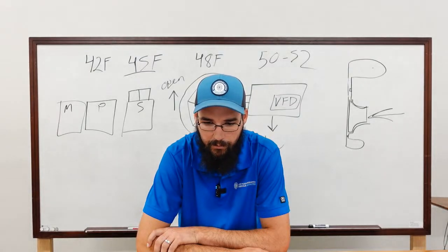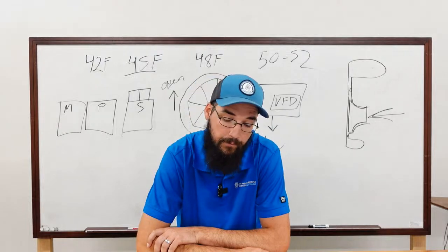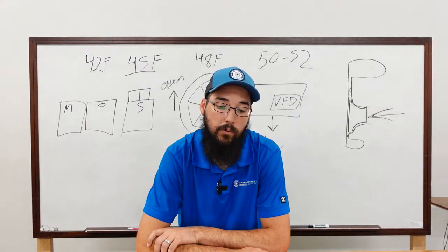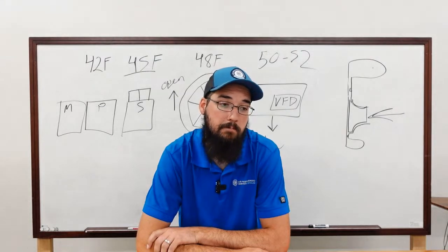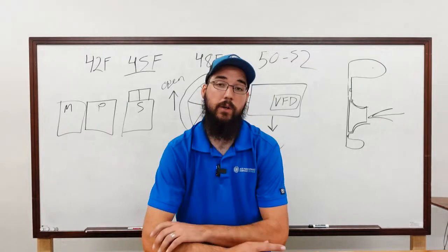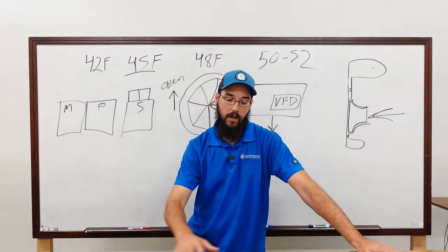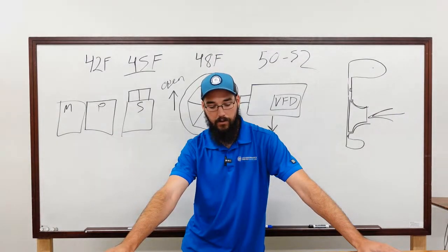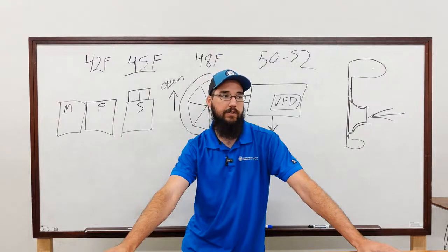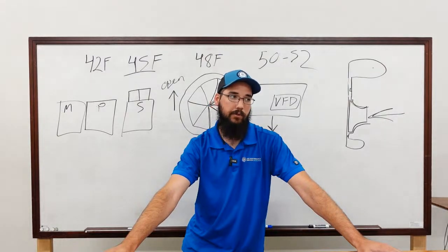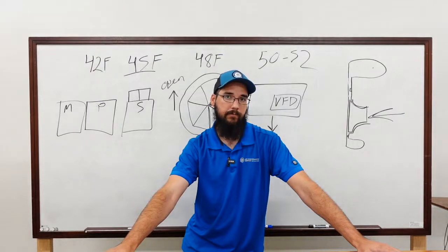So what condenser water temp would you say is good and what is too high on a centrifugal? Well, that comes back to your lift. You have to factor in your lift and your set point. So in a commercial cooling application like ours with a 45 set point, and depending on my chiller, I'm going to use a Trane CVH. I know that I can push that chiller, especially a CVHE, to where my inlet water is able to get right at the edge of 90 degrees, 88 to 90 degrees. When I get to that point and my entering chill water is floating in the mid 50s and I'm achieving 45 out, I'm riding that surge line for a machine that was designed for those conditions.